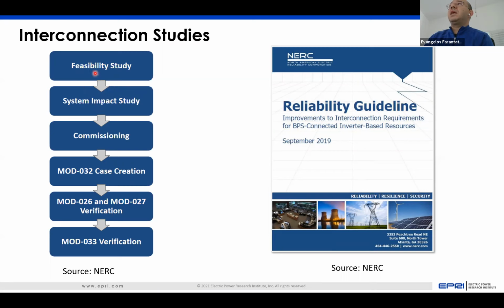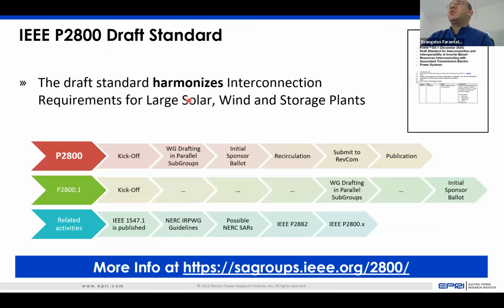At this stage, for these studies, we need generic models. The transmission planner does not know the specific model of the inverter or the vendor. Since how the inverter performs depends on how it is controlled, if you don't know the control settings, you cannot perform an accurate study. So there is a need for standardization in terms of the performance of those inverter-based resources.